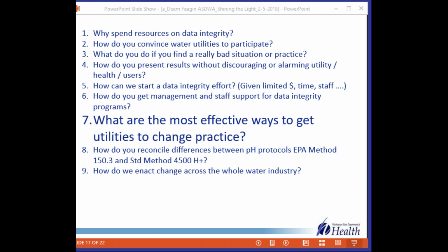The second thing is, if you can, try and make changes in the moment. If it's a setting and you can do it and the utility agrees, the error mode would be a good example of that. When we first started, we weren't confident enough because we were still learning what the settings meant. But now I just talk to the operator about what it means and ask them if they want to change it right now, and 100% say, well, yeah.